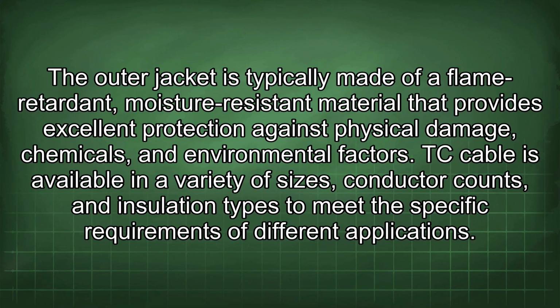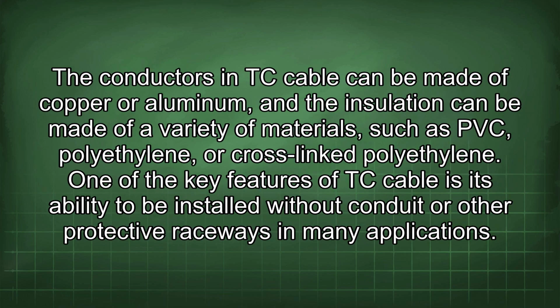TC cable is available in a variety of sizes, conductor counts, and insulation types to meet the specific requirements of different applications. The conductors in TC cable can be made of copper or aluminum, and the insulation can be made of a variety of materials such as PVC, polyethylene, or cross-linked polyethylene. One of the key features of TC cable is its ability to be installed without conduit or other protective raceways in many applications.